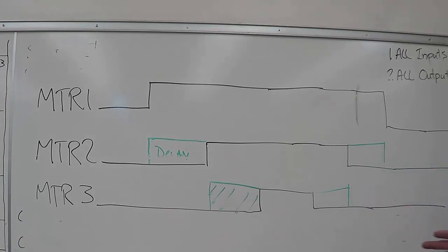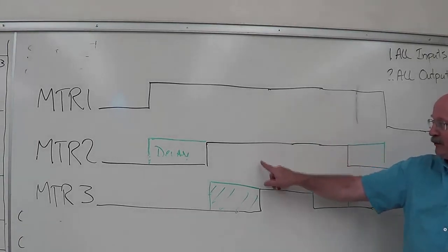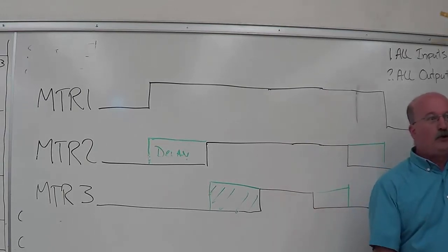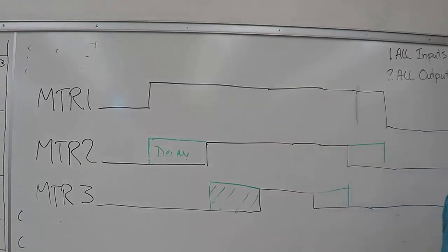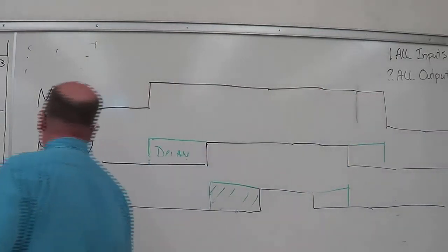I've gotten the delay period where people look at it and they put, if it's motor 1, motor 2, a huge number of rungs with a huge number of contacts. That whole thing can be simplified down to 2 contacts. Okay?